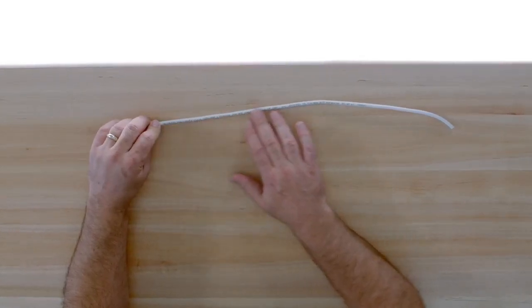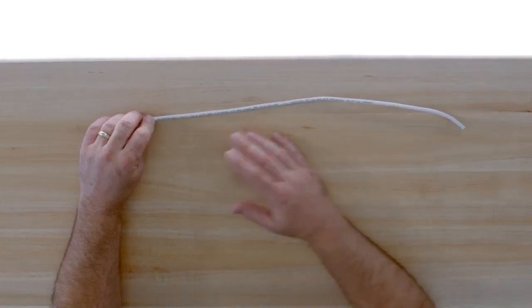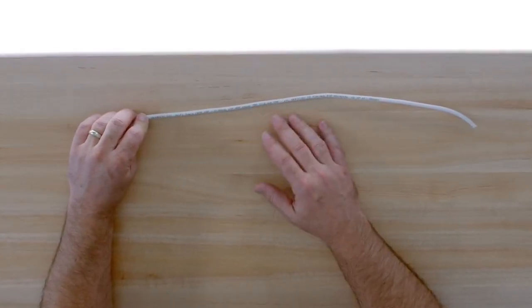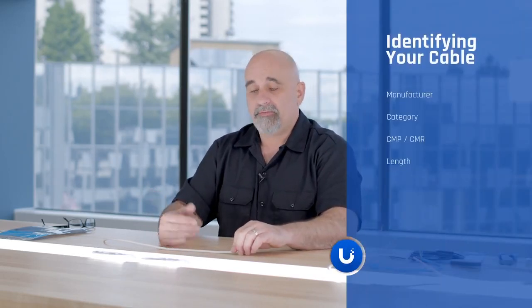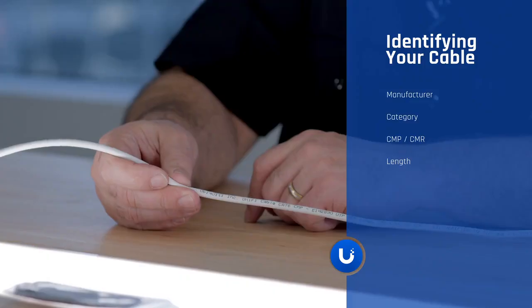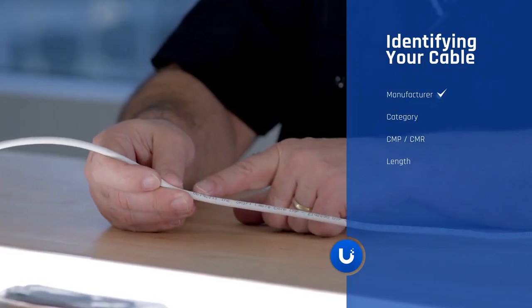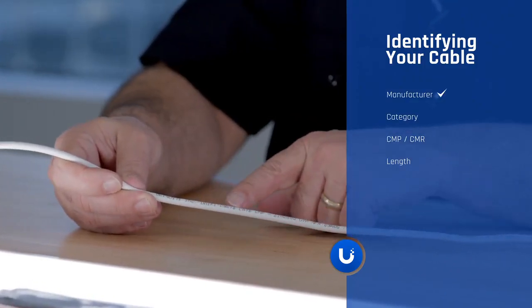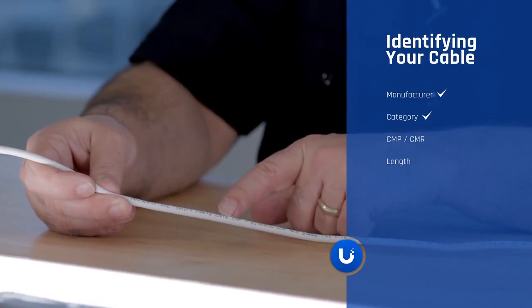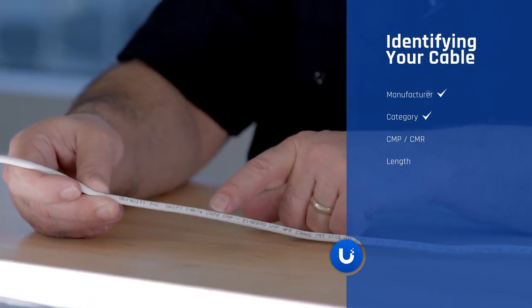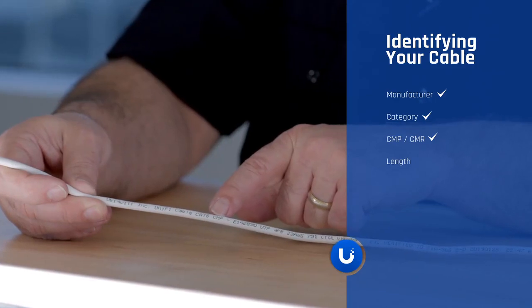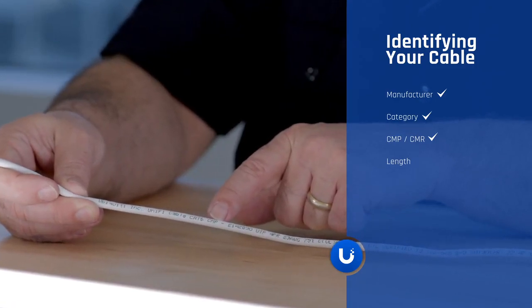So when you're looking at your category cables or Cat 6 cables, you're going to see there's a number of markings on here, and there's a couple of things I'd point out that you want to keep in mind. This might be if you're going into an existing building or your house and you're not quite sure what cable you have. It'll tell you typically who the manufacturer is. It'll tell you the type of category that the cable is. That'll also be with the CMP or CMR. That's going to let you know if it's plenum or riser cable.